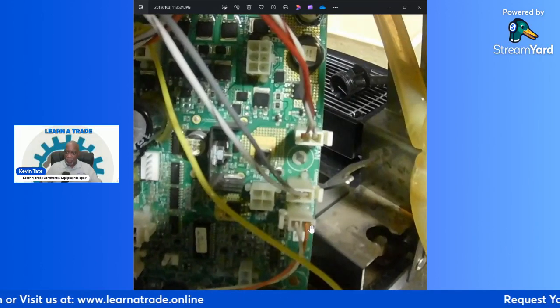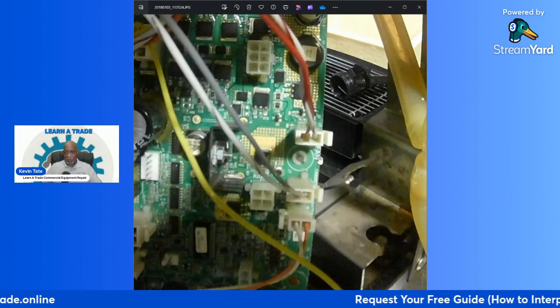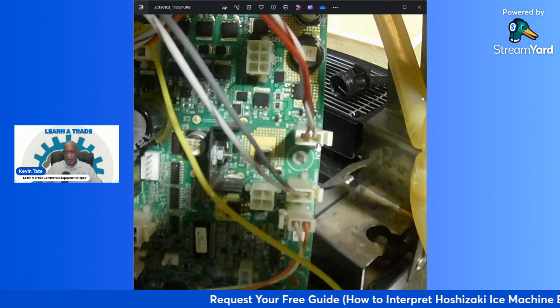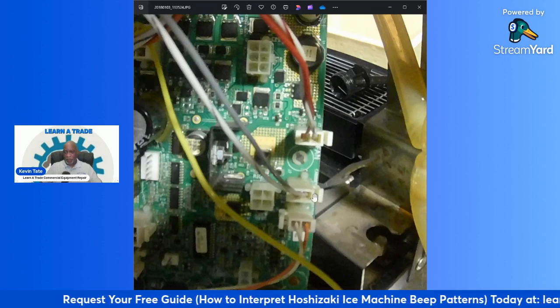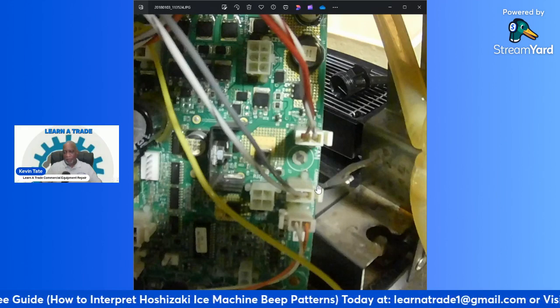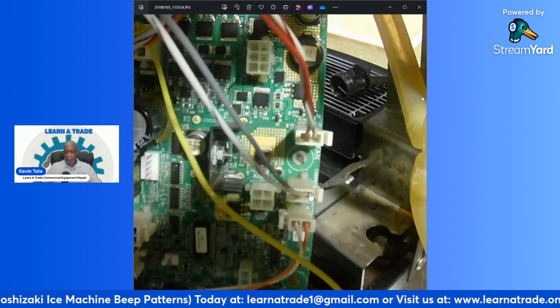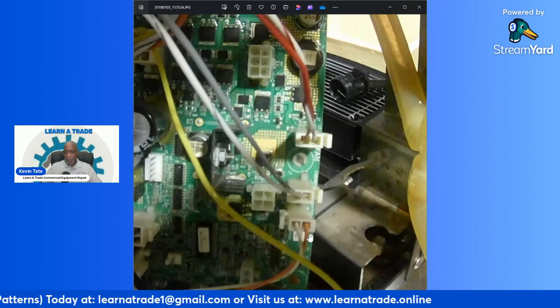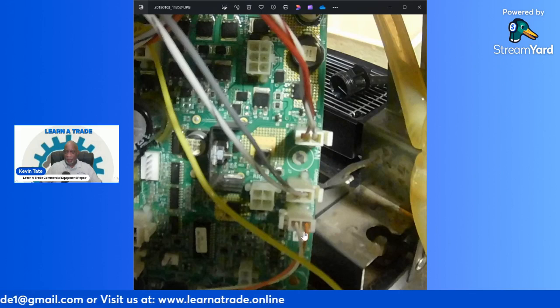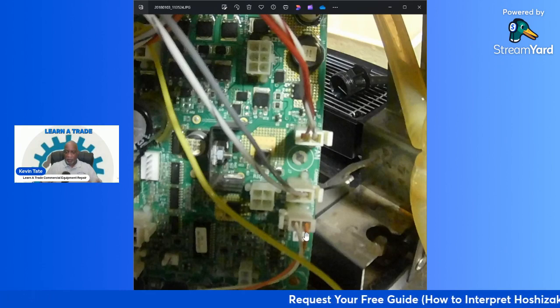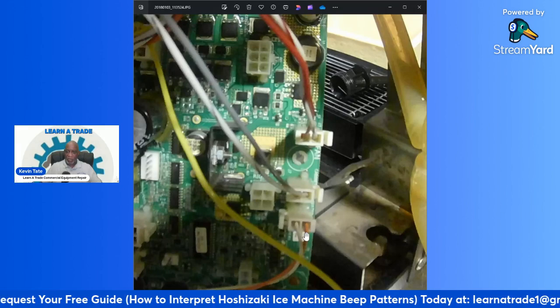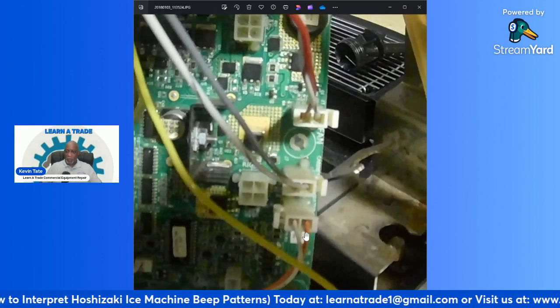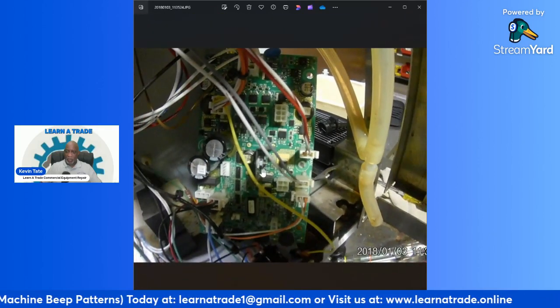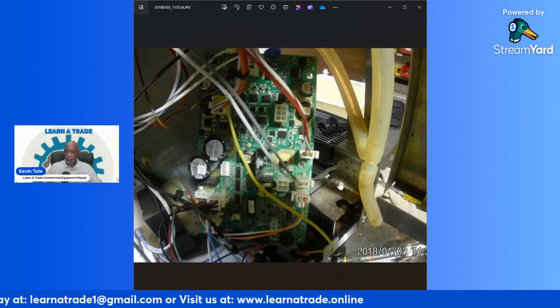Let me see if I can show it to you now. Right here, this one is for your fan. This is for your condenser fan. This one here, the gray and white wire, that's for your cabinet sensor. And this one right here, the orange and white wire on the bottom, that's for your water bath. So all of these communicate with the board, telling it what the temperatures are, what the water levels are, and stuff like that. It's always good to make sure you take a picture so you know where everything goes.